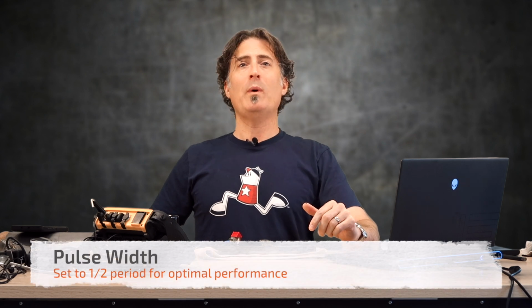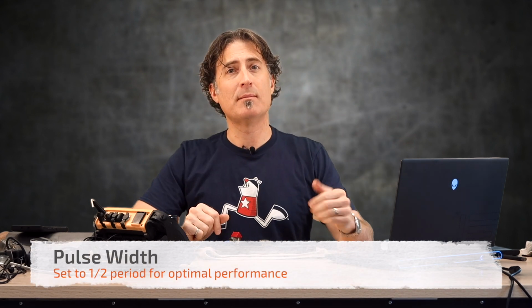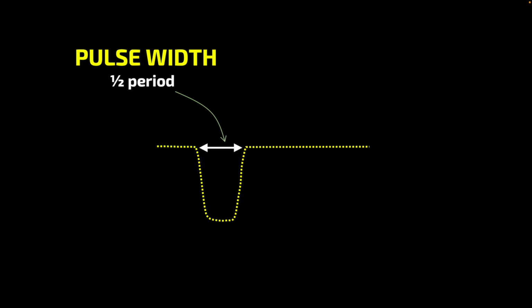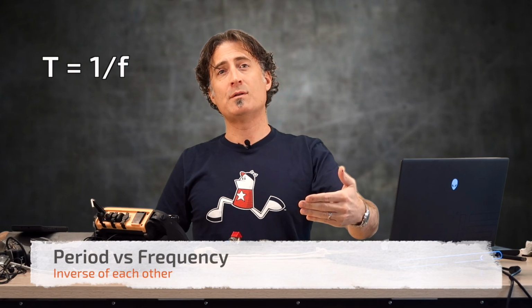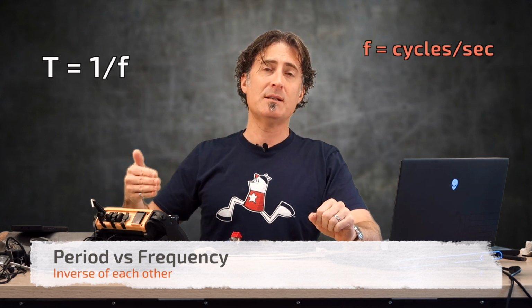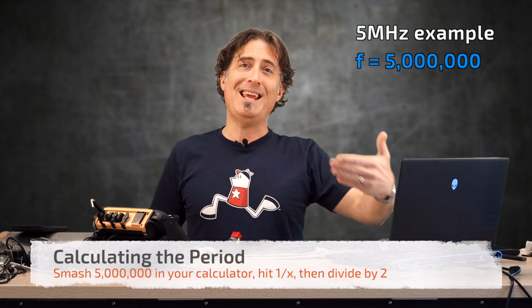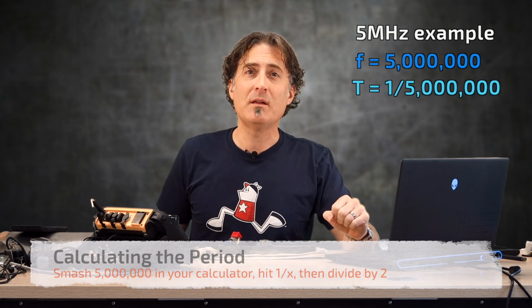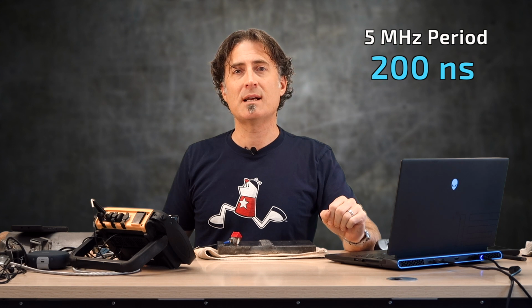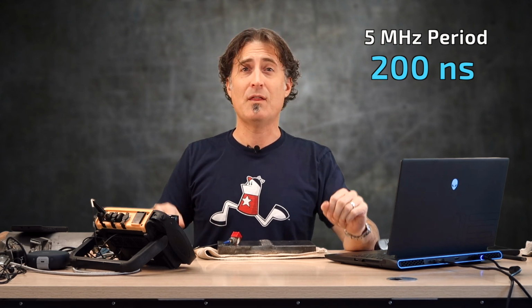Now, we can't really ask a drummer to do that, but we can certainly get the instrument to fire a square wave. Pulse width is how long we hold that negative square signal. And to get the most amount of sound power out of your transducer, you want to set this to half the period. Period is the inverse of frequency. Frequency is cycles per second, so period is seconds per cycle. For a 5 megahertz transducer, the period is the inverse of that, so 1 divided by 5 million is 0.0, a bunch of zeros, and then a 2, that's 200 nanoseconds or 200 billionths of a second. That's the entire period, so the setting for the pulse width should be half of that, or 100 nanoseconds.